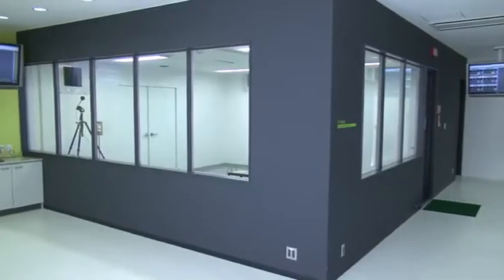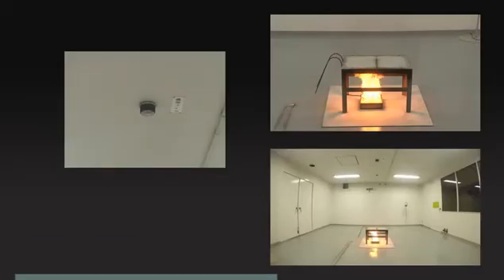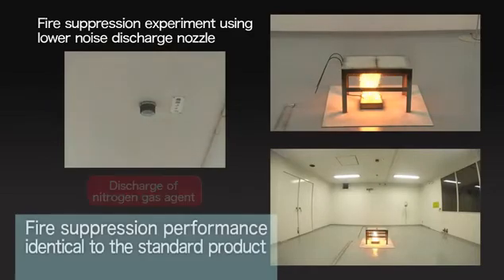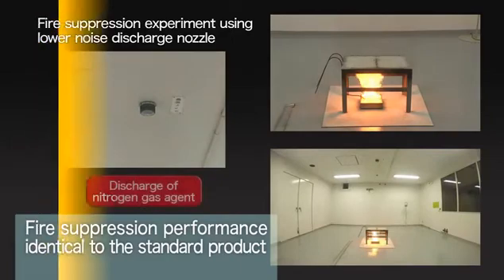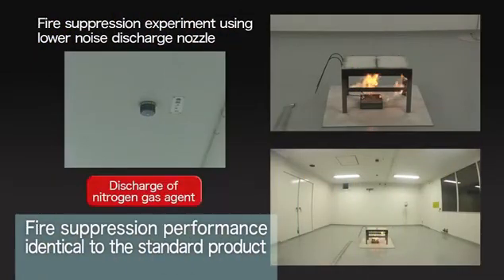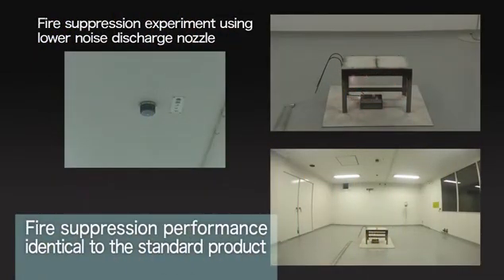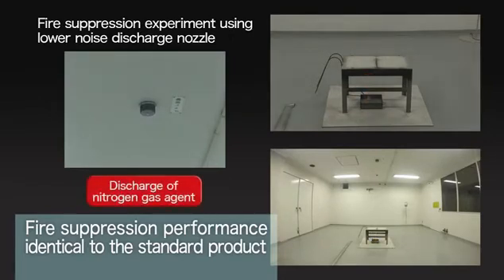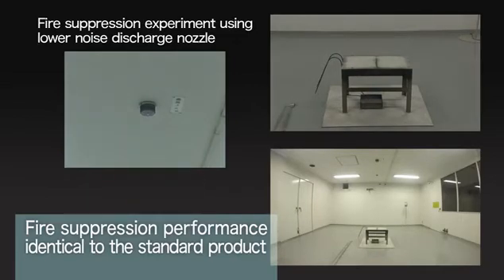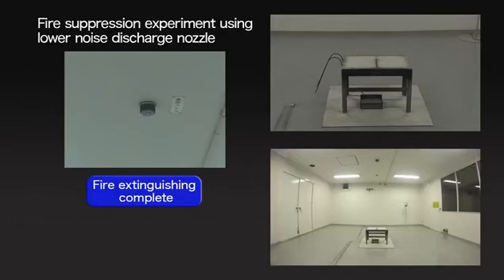In our case, the lower noise discharge nozzle that KOATSU was a leader in developing is compatible with fire suppression systems currently in general use and has achieved a gas discharge noise decibel level in the 90s. This approach of reducing the gas discharge noise minimizes the impact on hard disks. Naturally, fire suppression performance remains unchanged from standard products.